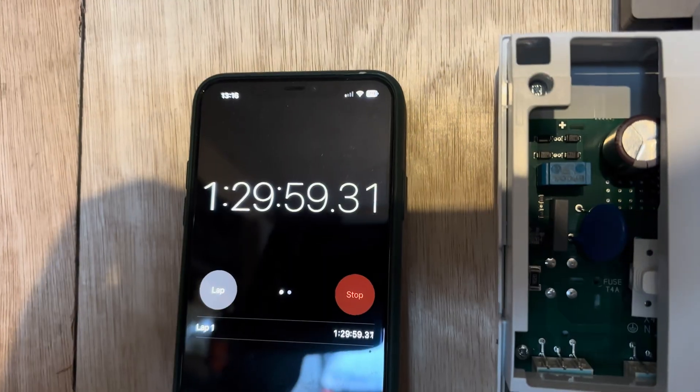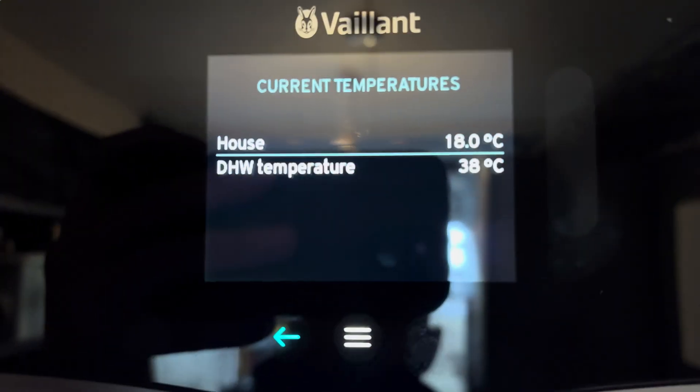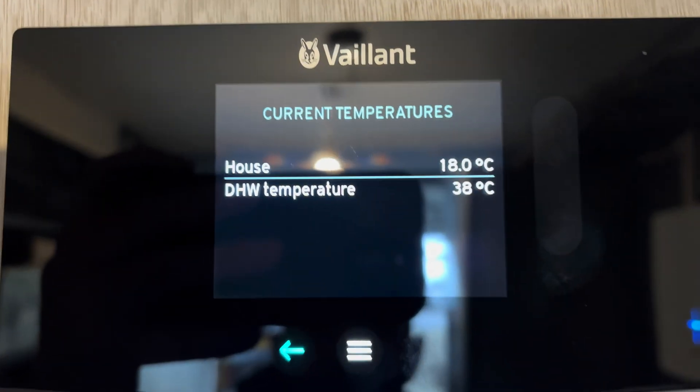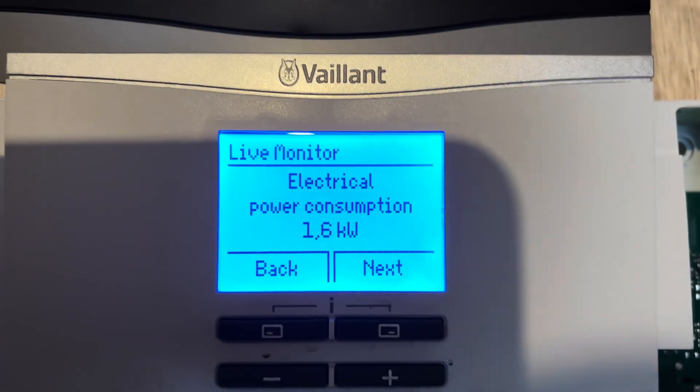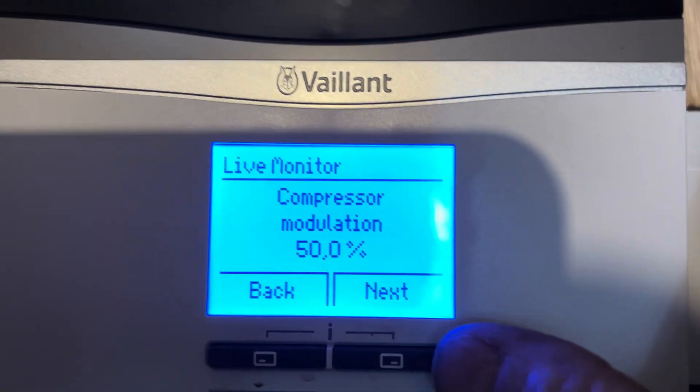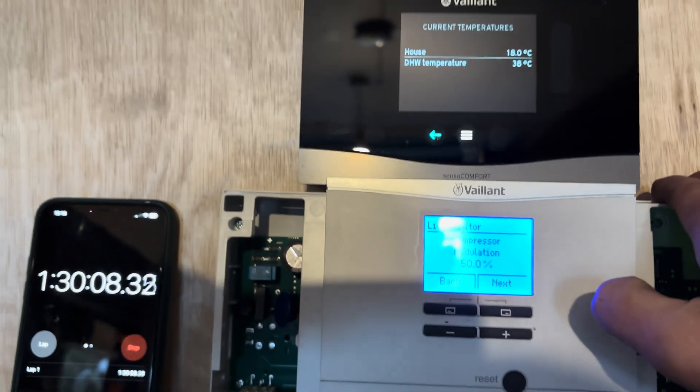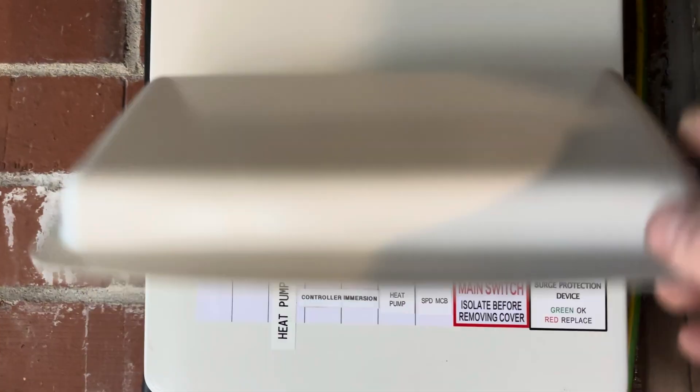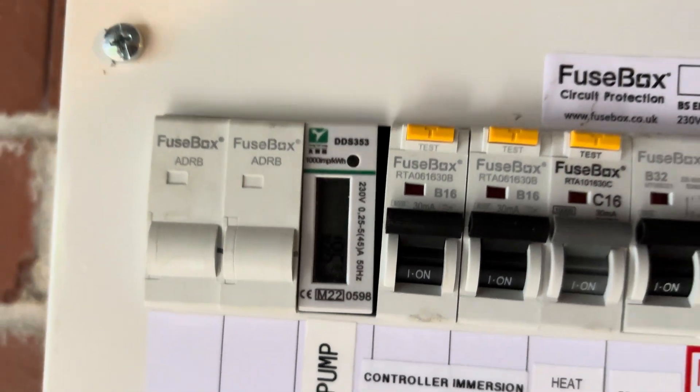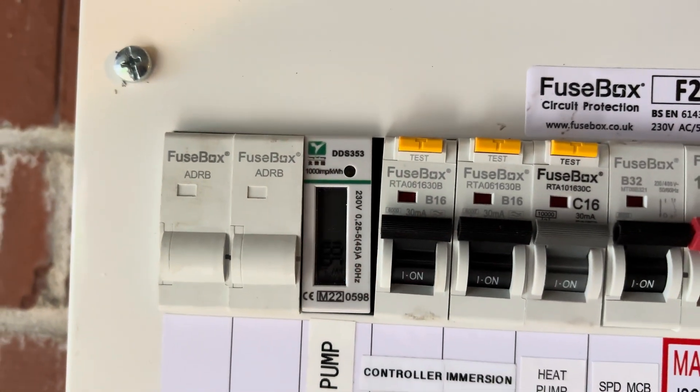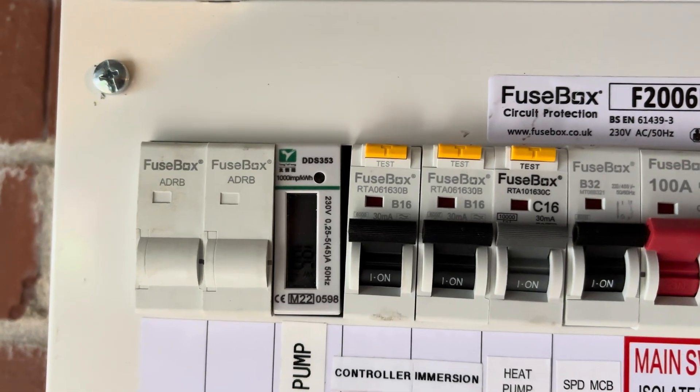Now just coming up to an hour and a half in. We're at 38 degrees C. Power electrical consumption 1.6 kilowatt. Modulation still at 50%. Looking at the meter, 1.85 kilowatts of electric used so far.